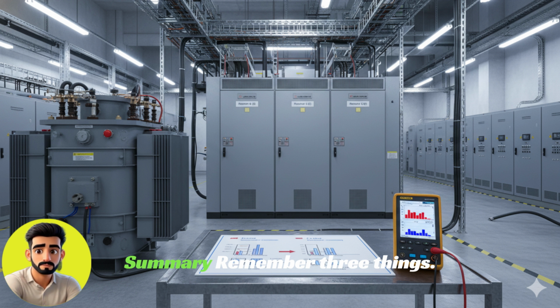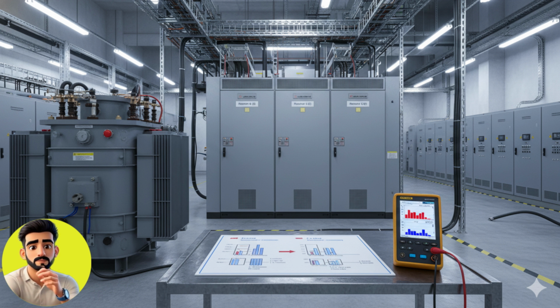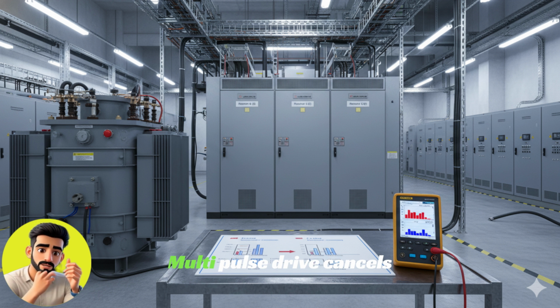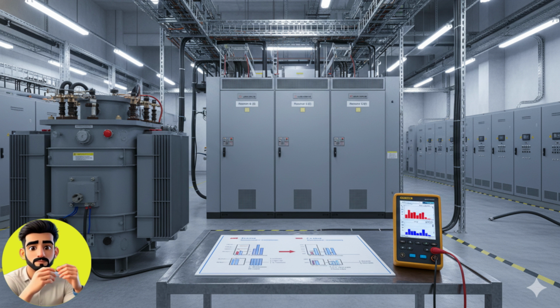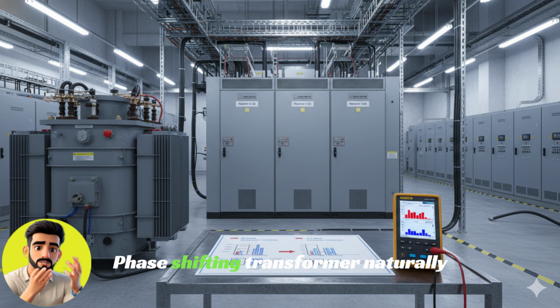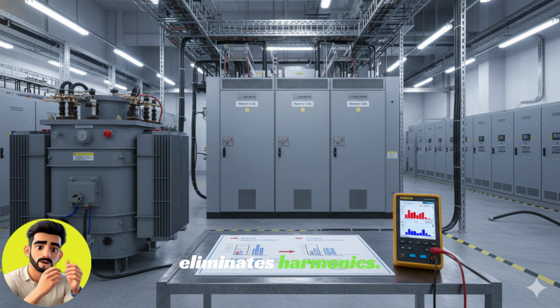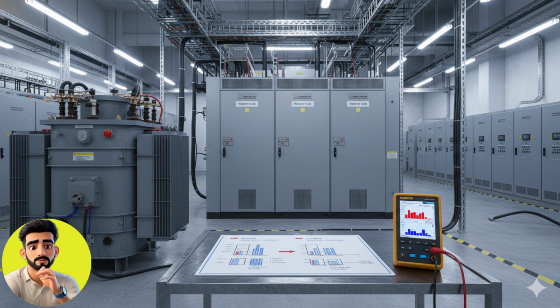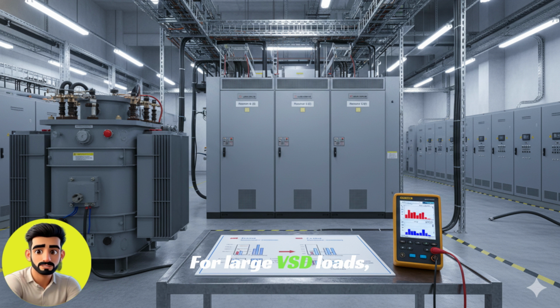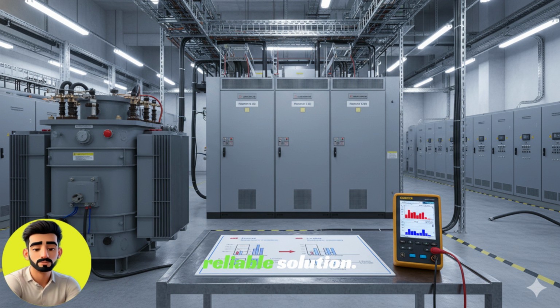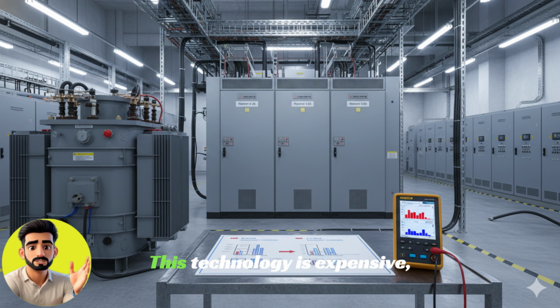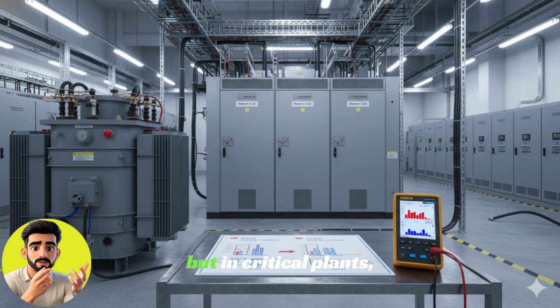Summary. Remember 3 things. 1. Multipulse drive cancels harmonics at the design level. 2. Phase shifting transformer naturally eliminates harmonics. 3. For large VSD loads, multipulse drive is the cleanest and most reliable solution. This technology is expensive, but in critical plants, this investment makes the system safe and stable.